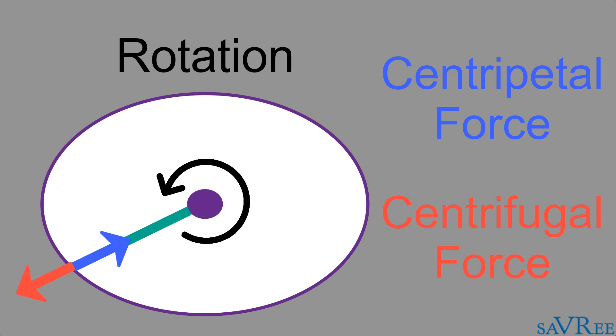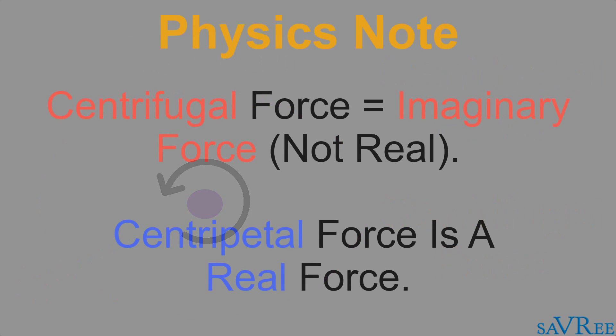Now, the impeller does the same job, although on a much smaller scale. It rotates very fast from a center axis of rotation. And the liquid that is drawn into the center is thrown outwards to the side, radially away from the eye of the impeller. This centrifugal force gives us a large increase in velocity, which we can later turn into pressure.